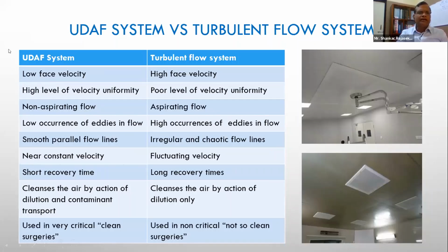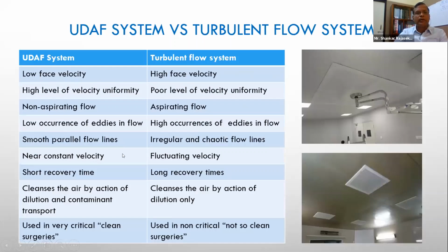So I've given some characteristics of the unidirectional flow and the turbulent flow system. It's quite self-explanatory. The main part of this is near constant velocity, which is a very important part. The velocity has to be constant; it can't fluctuate, number one. It has to be low face velocity, and it has to have a high level of velocity uniformity. So these three things are the most important aspects of a unidirectional airflow system: low face velocity, high level of velocity uniformity, and near constant velocity. Whereas in a turbulent flow system, it will be just the opposite.